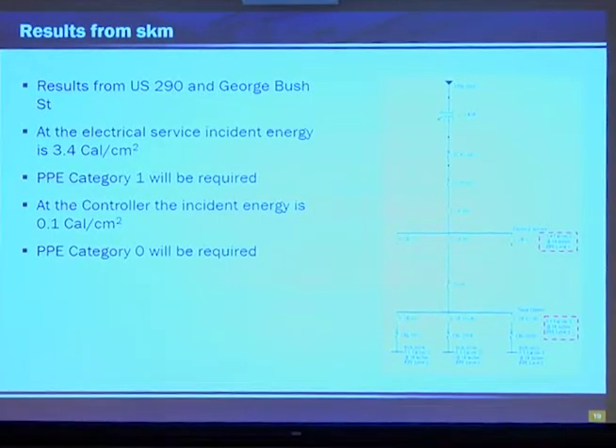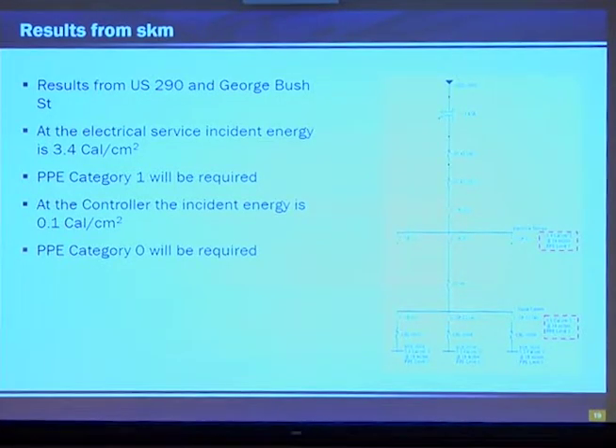Now, that information we ran in SKM, and the results show an incident energy of 3.4 calories per centimeter squared at the electrical service, and an incident energy of 0.1 calories per centimeter squared at the signal cabinet. In this real-world example, the worker will have to wear a Category 1 when servicing the electrical service. Or, if the worker is just troubleshooting the signal cabinet, he will have to wear a Category 0. Michael will continue with more examples.